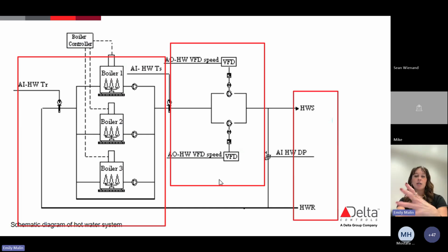And then our final one here, it's not really pictured, but let's just pretend that we do have a couple of different zones. Within those zones, we're going to see temperatures. So a thermostat, in the same way that we saw it in the zones of our VAV and air handling unit. It has a set point and it's saying, hey, the room is warm enough, or the room isn't warm enough. If the room is too cold, again, it's going to start to open a valve. And it opens that valve to let more hot water flow through the radiator or air handling unit, whichever you're using, in order to release that heat into the space.